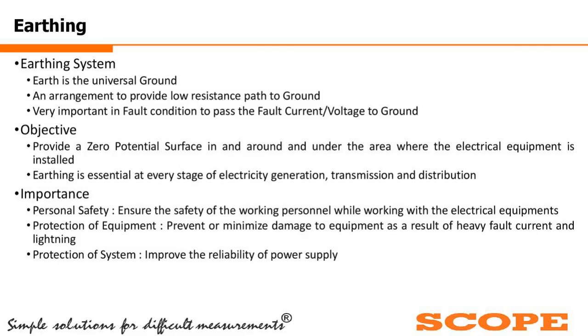The importance, as we all know, is that it provides personal safety of the user, that is, safety of working personnel while working with electrical equipment. It also gives protection to the equipment, whether it is a testing instrument or other instrument operated by electrical power. It prevents or minimizes damage to the equipment as a result of heavy fault current and lightning. And lastly, it protects the system. It improves the reliability of the power supply, including the generator.